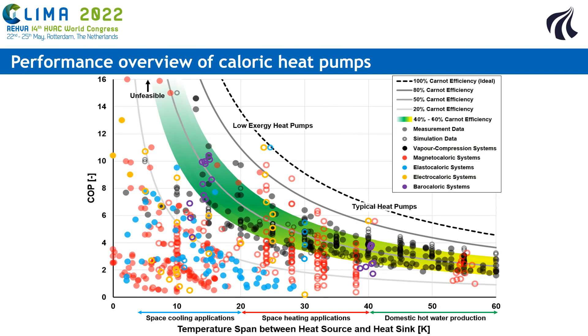This figure gives an overview of the performance of caloric heat pump systems when compared to conventional heat pumps. You can see the COP as a function of the temperature span between the heat source and the heat sink. The full circles are experimental data, while the rings are simulation data. Vapor compression heat pumps have typically a Carnot efficiency between 40% and 60% for building applications. The performance of most caloric heat pump prototypes is often below 20% Carnot efficiency and with a maximum temperature span of 30 kelvin. However, for a temperature lift around 20–25 kelvins, the best magnetocaloric heat pumps have a COP that is similar or higher than vapor compression heat pumps. Simulations suggest that magnetocaloric heat pumps could maintain 60% Carnot efficiency for higher temperature spans of 50 to 60 kelvins. The best elastocaloric heat pump prototypes have a Carnot efficiency of around 20%, with two prototypes reaching around 40% efficiency for temperature lifts of 10 to 16 kelvins.